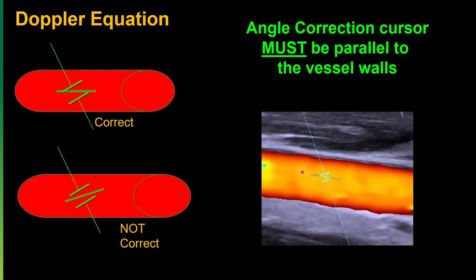Somewhere on your system will be a readout as to what that angle correction is. In other words, where it sits, there's no vessel or anything on here, just the box is at 60 degrees, and it tells me that up here. I can change that somewhere on my system. Some systems have presets like 0, 40, 60, 80, whatever. And then they also let you make a fine adjustment, if you will. If you're at 50 and you need to move it some more, then it might go, say, to 53.